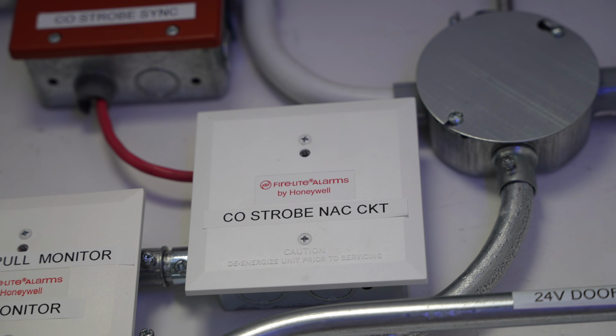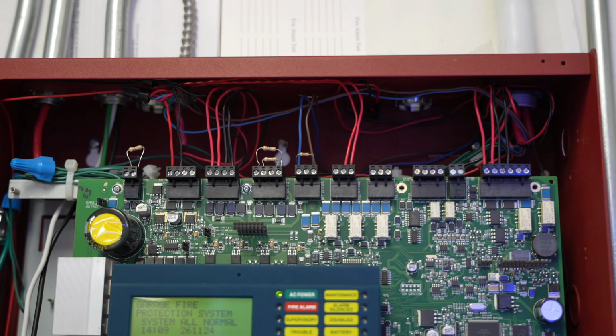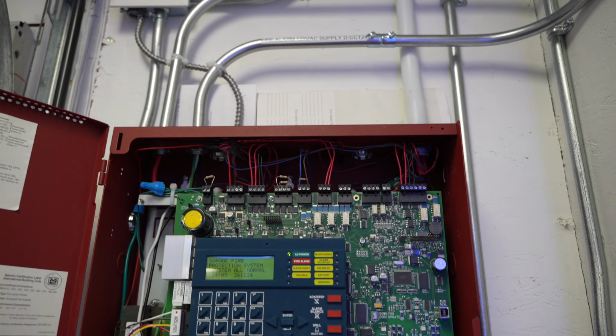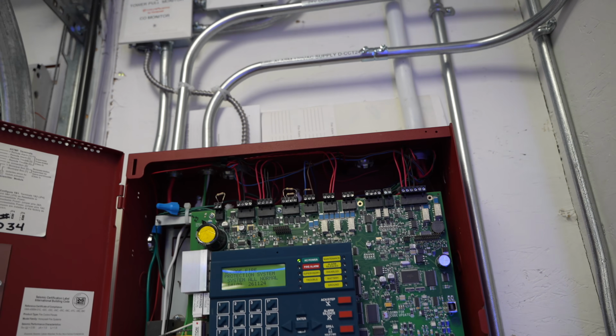And also on zone 10 is this control module here, because I remember I couldn't set the NACs on this to zone 10 specifically and have them only go off on a supervisory but not on a fire. There was some combination of the NACs just weren't going to do what I needed, so I had to use a control module, because the control module I could zone more specifically the way I wanted.